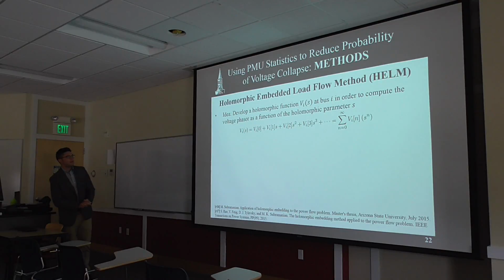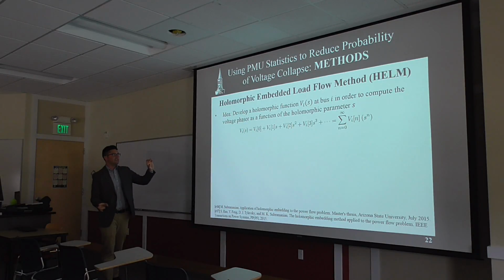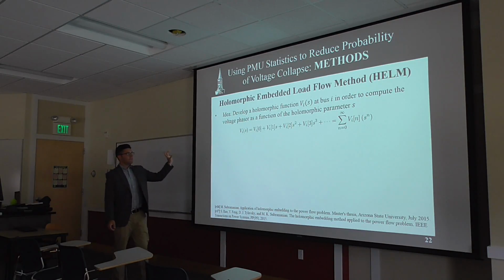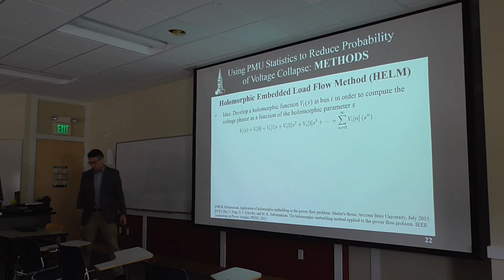The second tool that we've decided to leverage is the holomorphic embedded load flow method, or HELM. And the idea behind HELM is instead of solving power flow using traditional iterative techniques such as Newton-Raphson, we develop a holomorphic function, E of S, at each bus in the system. And that holomorphic expression can be expressed as an infinite power series, as shown here.